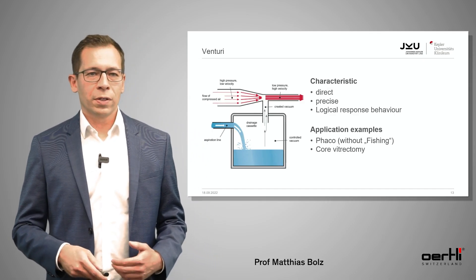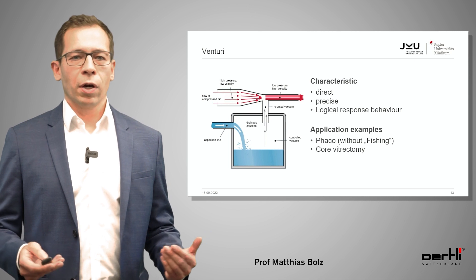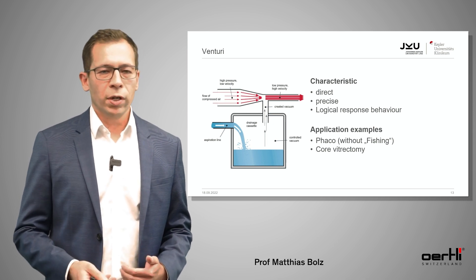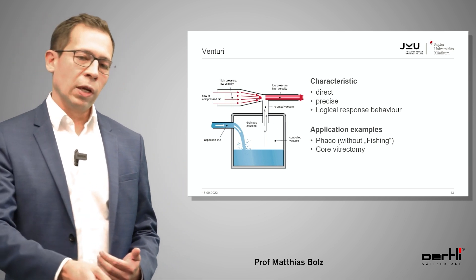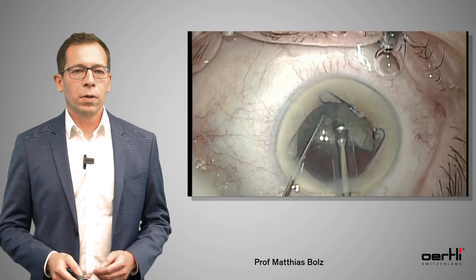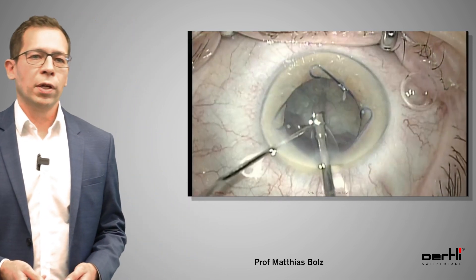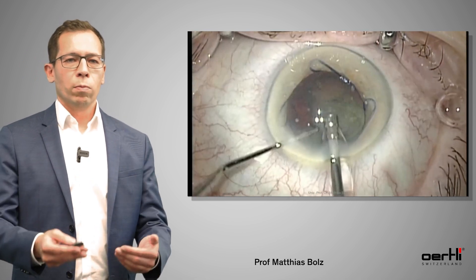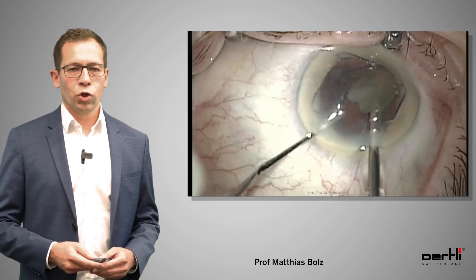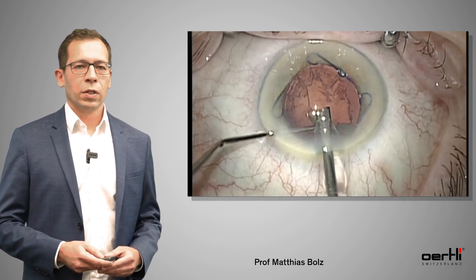The characteristics of the Venturi pump are that it's very direct, very precise, and has a very logical response behavior — it's really like driving a car. As soon as you press the pedal, you immediately have a vacuum. Application examples are phaco without fishing: it's not the phaco tip that moves to the lens, it's the lens that moves to the phaco tip. You can also always use it for core vitrectomy. As you can see in this example, there's much more turbulence in the anterior chamber and all the fragments really move to the phaco tip. If you're a rather experienced phaco surgeon, I would recommend using Venturi — it's very fast and very simple.